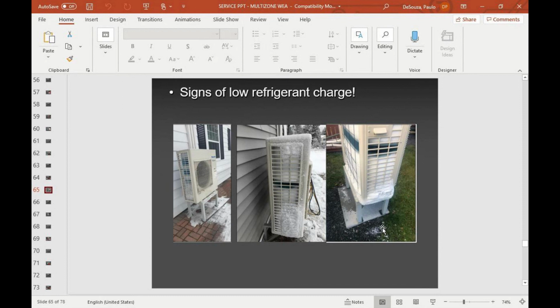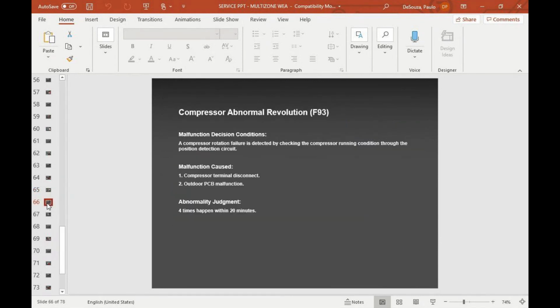F91, in most cases, like I think 99.9%, was lack of gas, a shortage. There was a leak. The guy recovered everything, checked for leaks, repaired the leak, and everything was up and running. So when you have a multi-zone, these are live pictures from the job site, guys. If you see your multi-zone looks like this, I can tell you 99.9% you are low on refrigerant. These three outdoor units are from three different job sites, and all had about 1.6 to 2 pounds lack of refrigerant.